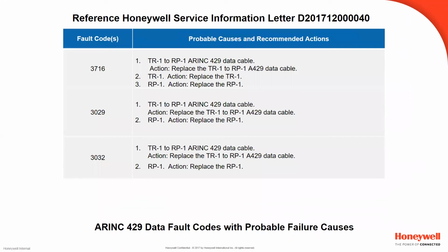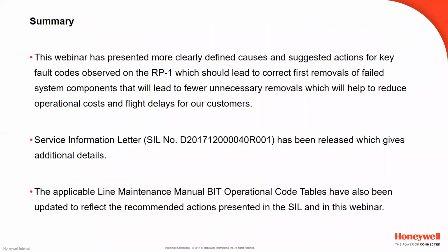With this, we come to an end of the troubleshooting guidance for NFF reduction. And to summarize, this webinar has presented a more clearly defined cause and suggestive actions for the key fault codes observed on the RP1 radar processor, which should help you to lead to correct first removals of failed RDR-4000 system components. And with that, it will lead to fewer unnecessary removals, which should help reduce your operational costs and flight delays.